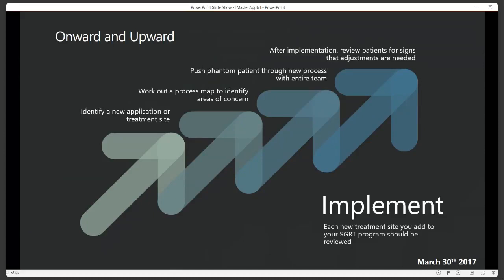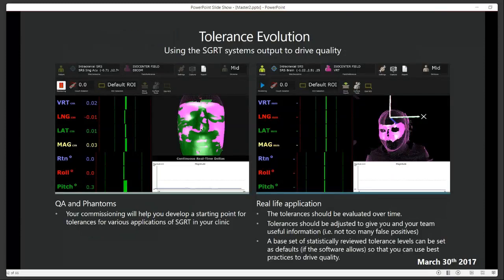You identify new applications. If you did it for breast and your doc says, I want to do SRS, you do more performance validation. You work out a process map to identify areas of concern and where any type of failure modes could exist. Push a phantom through the process with your entire team. That should be in red, very important. And then after implementation on actual patients, review the patients for signs that adjustments are needed. That allows you to constantly be adapting your process and constantly be addressing concerns and frustrations so that you don't relegate it to nothingness in your clinic or collecting dust.